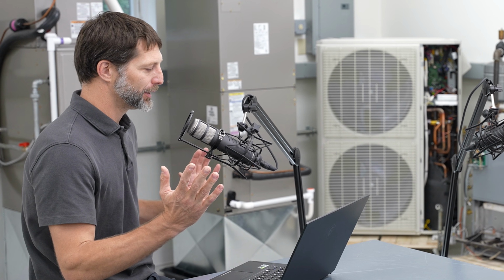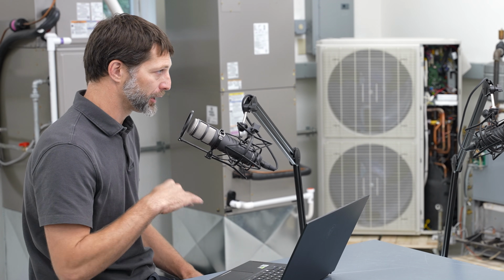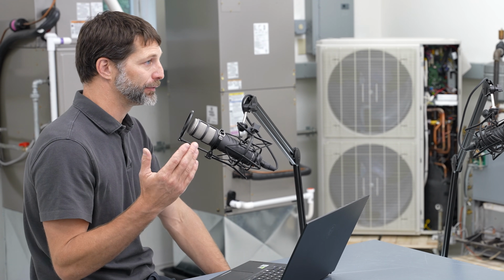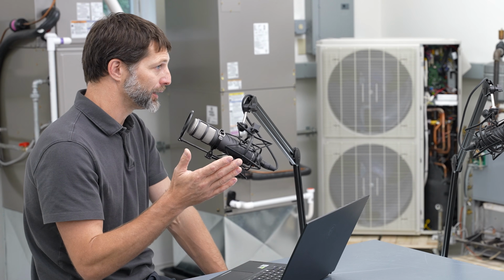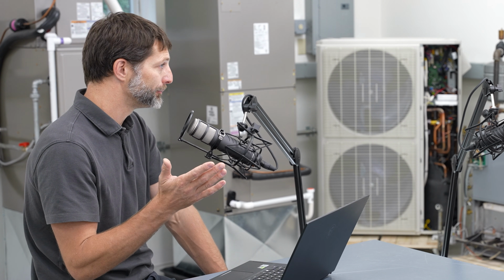But you can check this with static pressure. If you have a high pressure drop across that coil, you can know that you have a restriction there. And so if a customer hasn't changed their filter, or the filter is in there and kind of collapsed on itself and the air is getting around it, you can basically figure that that coil has got some dust on it. And that coil accumulates dust because in air conditioning mode, it's wet. And so any dust just gets stuck right to it. And then it just makes a mat. If you have pets in there, it's just going to accumulate on the bottom.